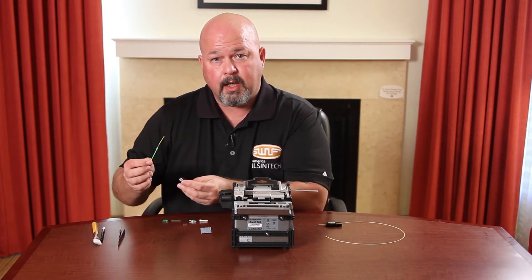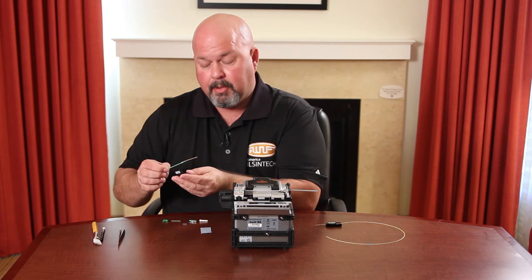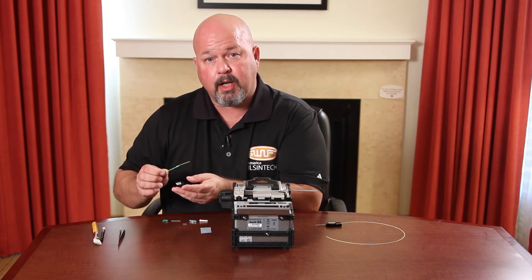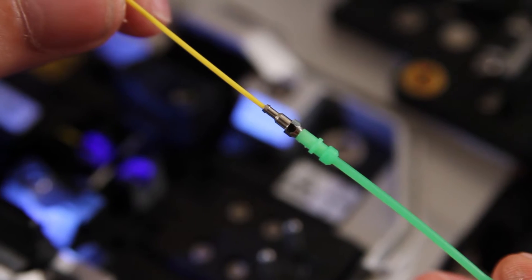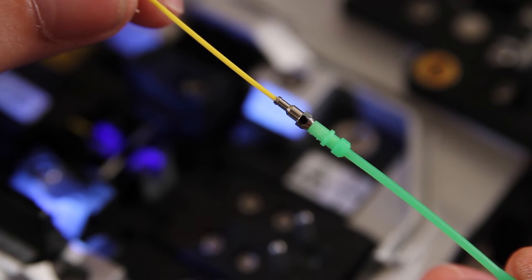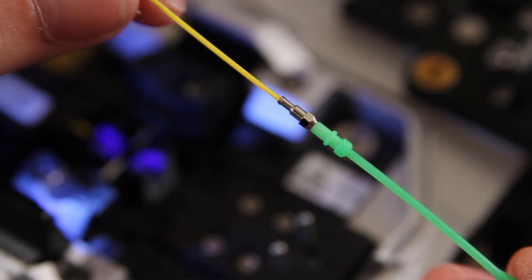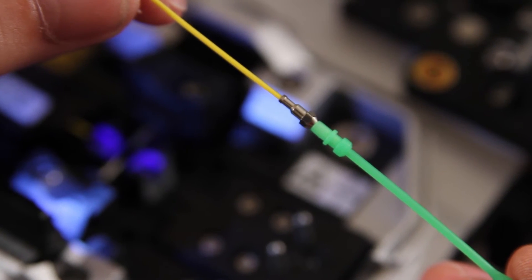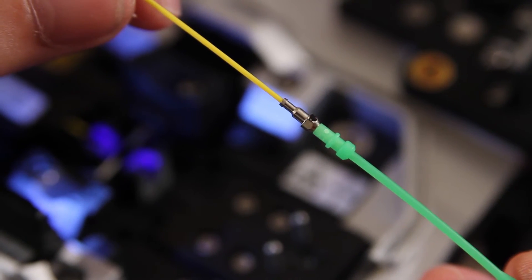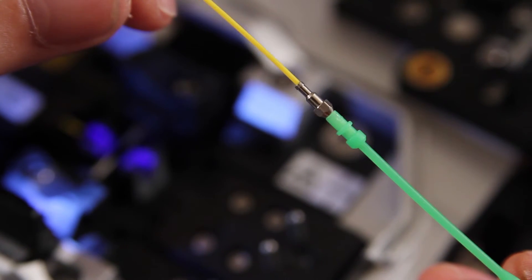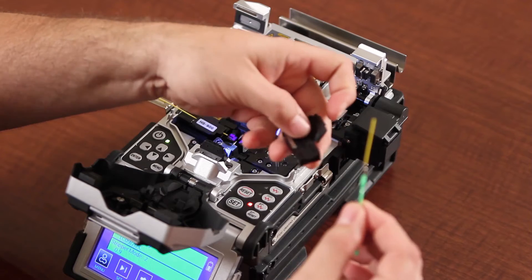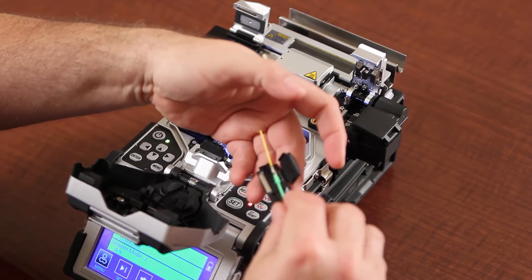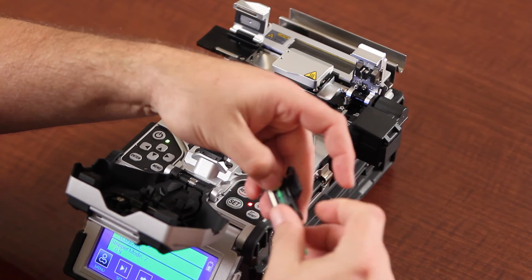With the LC connector, position is critical to the performance. On the face, one of the hexes, there is a black dot. Black dot is up. That is the proper angle of your connector.